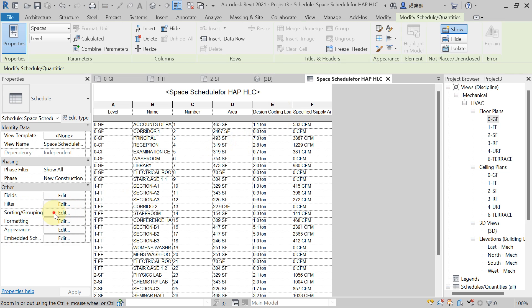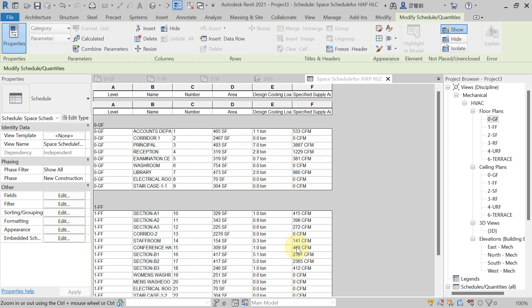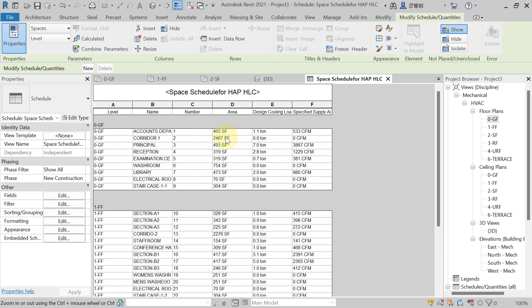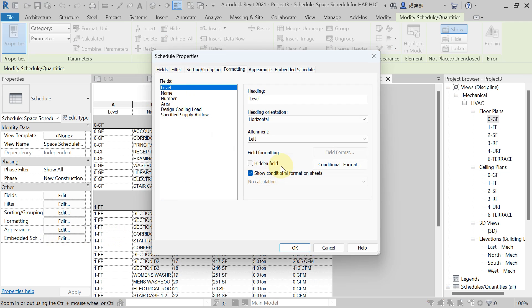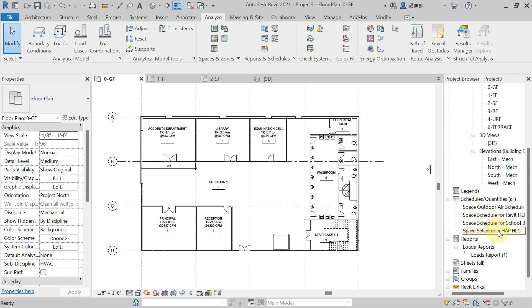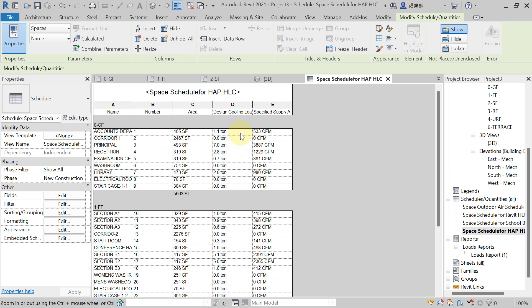In Sorting and Grouping, sort by Level. Select the total in header/footer, and add a blank line if you want. In Formatting, select the Level field and check Hidden. For the Area field, select Calculate Total in formatting. Now the area is visible. This is how you create the space schedule for HAP heat load calculation.